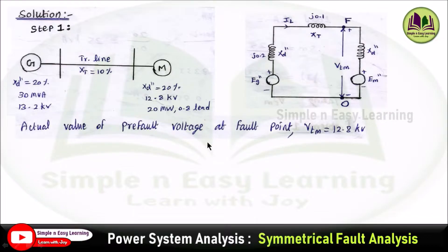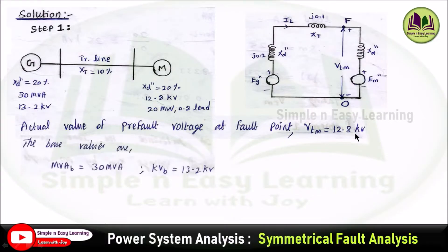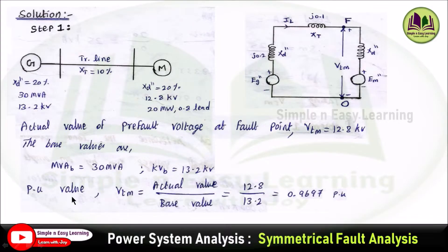The actual value of pre-fault voltage at the fault point equals 12.8 kV, so before the fault, this terminal voltage equals 12.8 kV. The base values are MVA_B = 30 MVA and kV_B = 13.2 kV. If base values are not given, we consider the generator ratings as base values. The per-unit value of V_TM equals actual value divided by base value: 12.8 kV divided by 13.2 kV equals 0.9697 per unit.